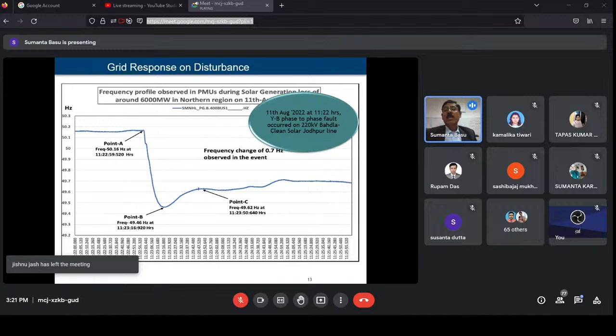So this is 11th August. A YB phase-to-phase fault occurred on a 220 kV transmission line, the Bhadla Clean Solar Jodhpur line. What happens is that almost all the renewable energy stations connected to this transmission line dropped their generation. It covered Bhadla 1, Bhadla 2, Fatehgarh, Bikaner, all those.